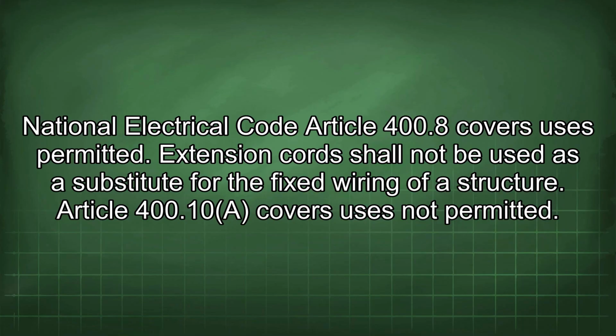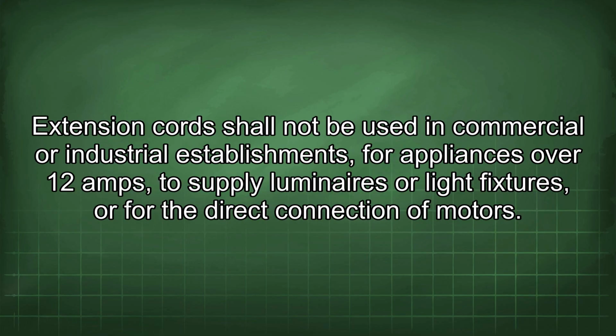National Electrical Code Article 400.8 covers uses permitted. Extension cords shall not be used as a substitute for the fixed wiring of a structure. Article 400.10 covers uses not permitted. Extension cords shall not be used in commercial or industrial establishments for appliances over 12 amps, to supply luminaires or light fixtures, or for the direct connection of motors.